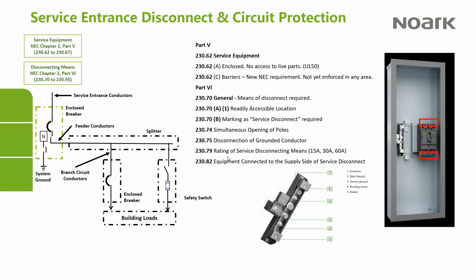The rating of the service disconnecting means. So this is a fairly complex clause in the code. Basically, what it says is that for very small services serving a single circuit, so think of what you see on utility poles where there's a cable TV box and it needs to have power. You'll see a very small load center. That'll be a service entrance load center, and that means that the minimum rating is 15 amps for that device. If that same small service is serving 2 circuits, then the minimum is 30 amps. And then for residential services, the minimum is 60 amps.